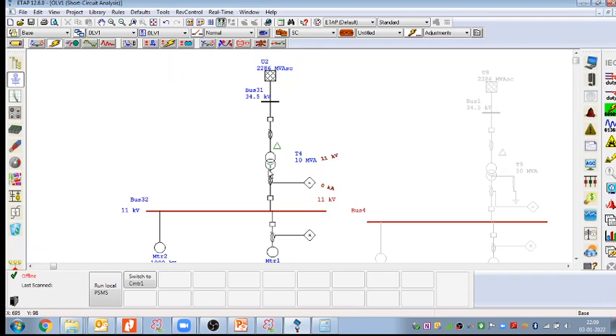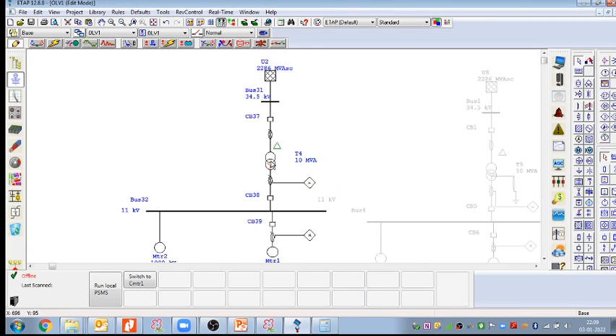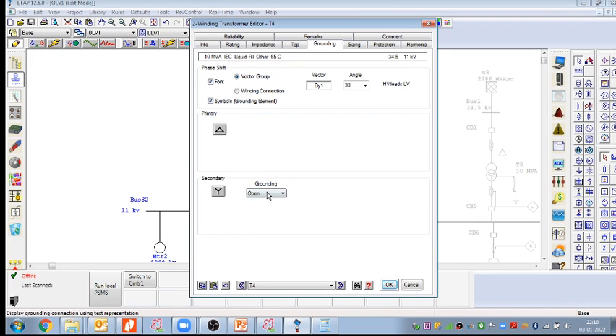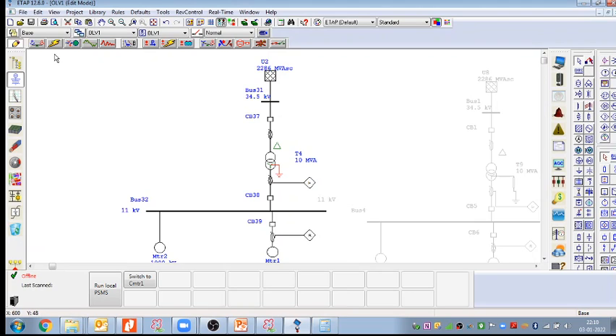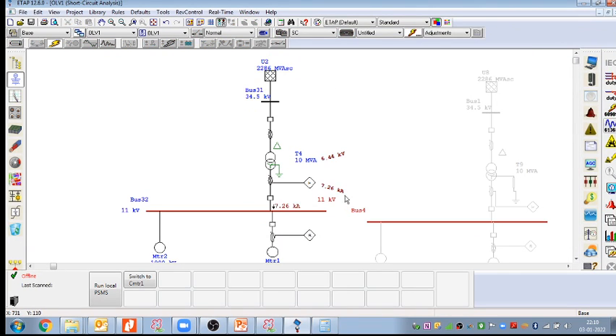Okay. So what is my statement here? If the system is ungrounded, then the line to ground fault current we cannot sense, and that is why we have to provide the grounding for the transformer neutral. Okay. Once we provide the grounding here, we take the next second case. Now we have provided the grounding, and when we do this simulation again, this is coming 7 kiloampere. So this grounding is providing the return path for the fault current, and we can sense it, and we can do the protections here, right?